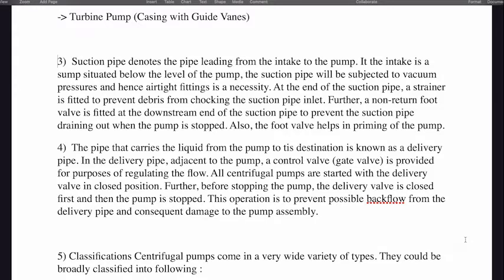The pipe that carries the liquid from the pump to the destination is known as the delivery pipe. In the delivery pipe adjacent to the pump, a control valve or gate valve is provided for the purpose of regulating the flow. All centrifugal pumps are started with the delivery valve in the closed position. Before stopping the pump, the delivery valve is closed first and then the pump is stopped. This operation is to prevent possible backflow from the delivery pipe and consequent damage to the pump assembly.